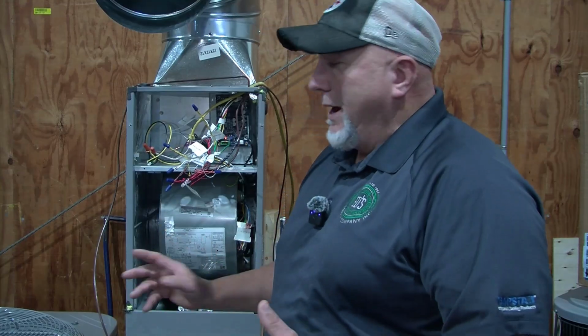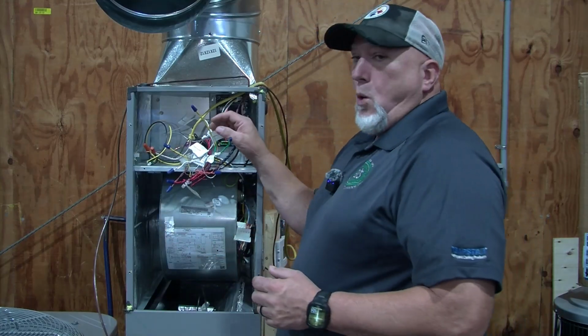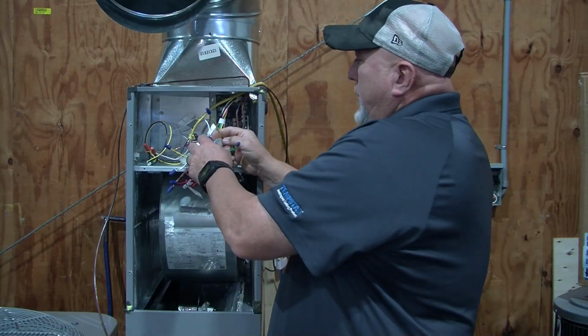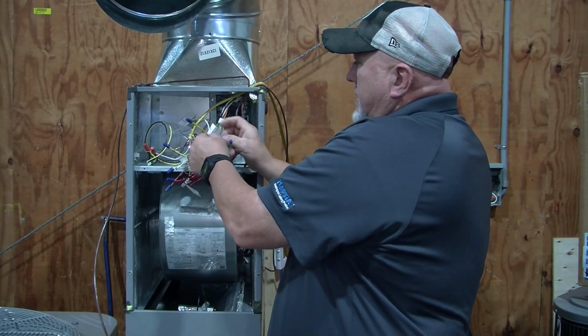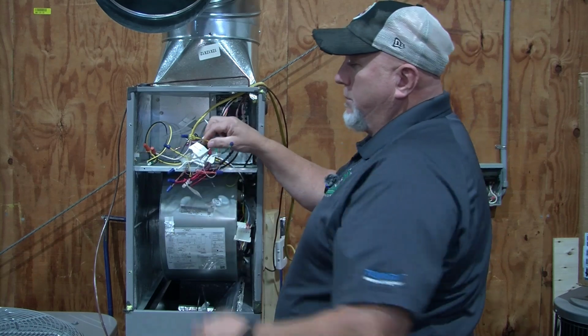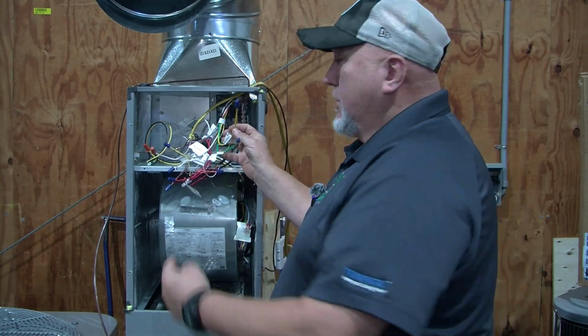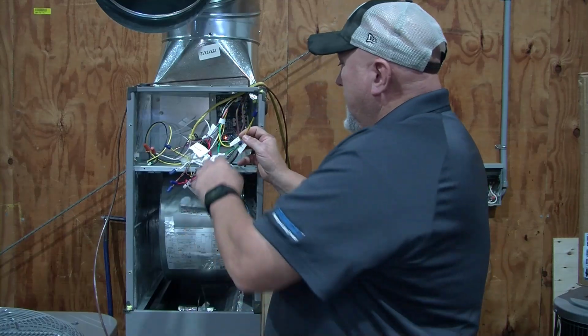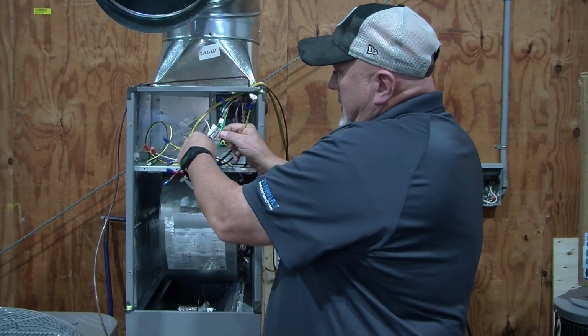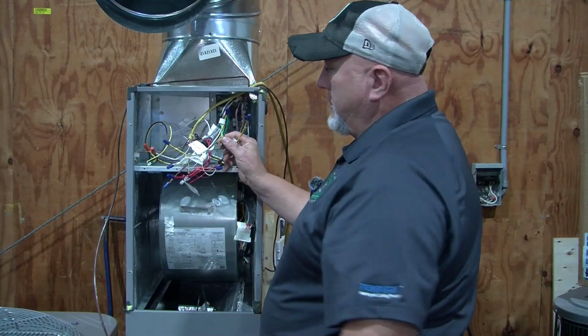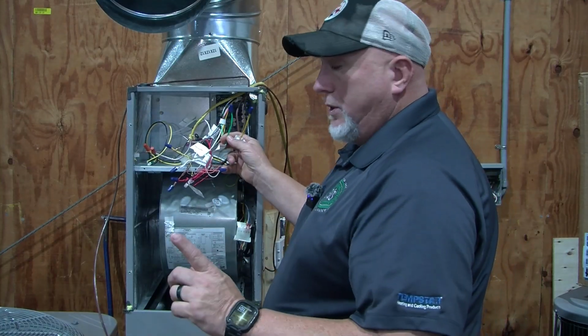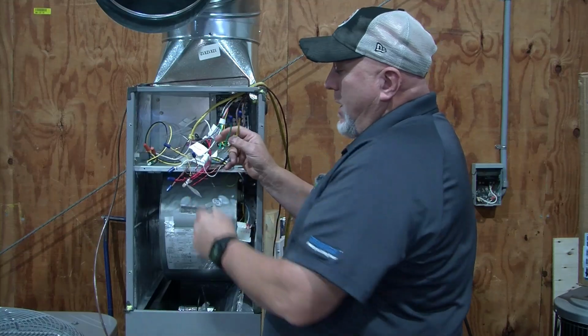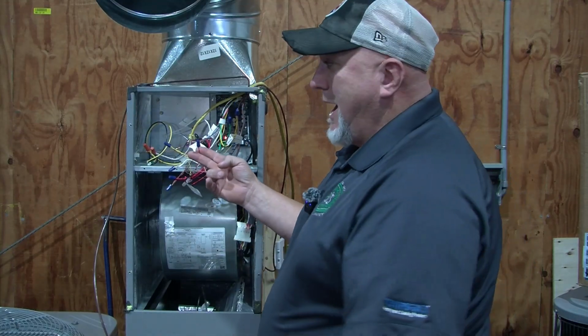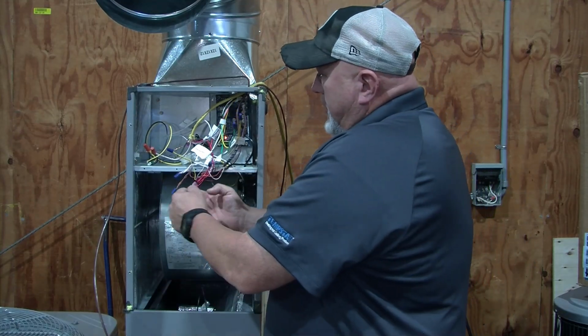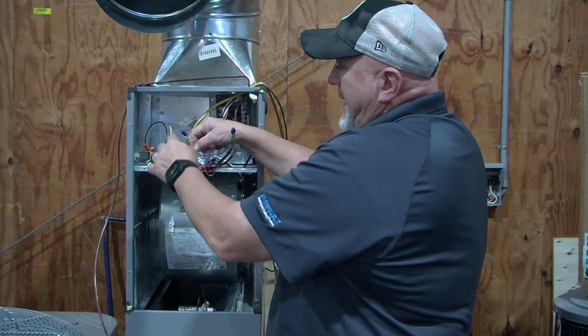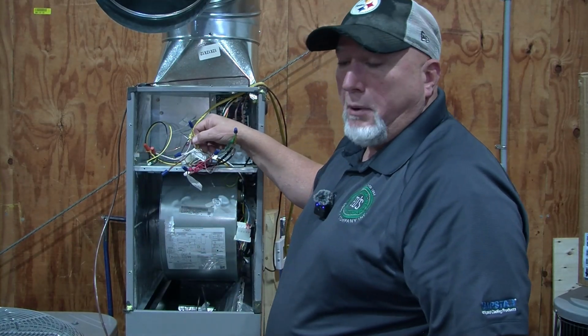So real quick, while we're waiting for the condenser unit to come on, we're going to go over what the wiring diagram is. You have a yellow in to thermostat. So your solid yellow goes straight to the thermostat wire. Your green is G in to the thermostat. It goes to the thermostat only. Your reversing valve goes straight to the outdoor unit. Your yellow for the outdoor unit is attached to yellow with purple.